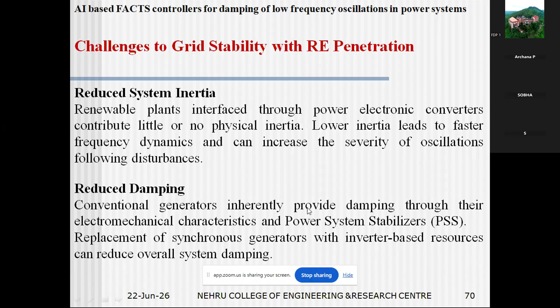Similarly, reduced damping. Conventional generators inherently provide damping through electromechanical characteristics and power system stabilizers. Power system stabilizers act through the excitation system. That provision is also absent. Replacement of synchronous generators with inverter-based resources will reduce overall system damping because PSS cannot act through inverter-based resources. There also, damping has come down.